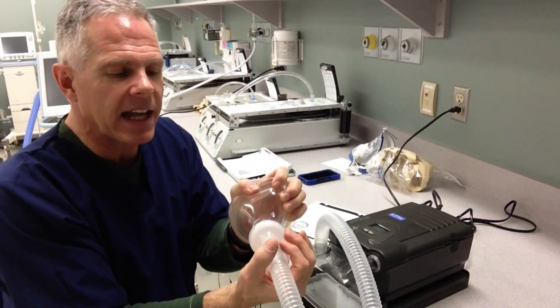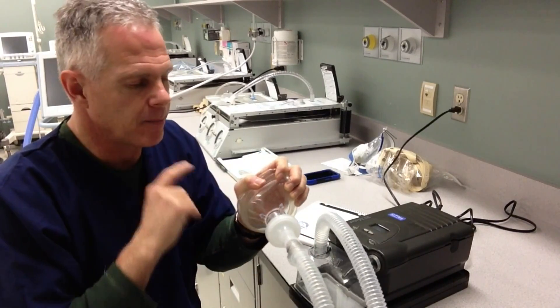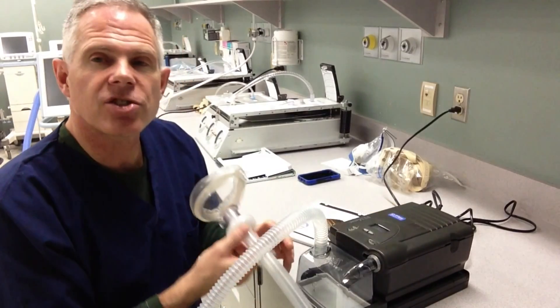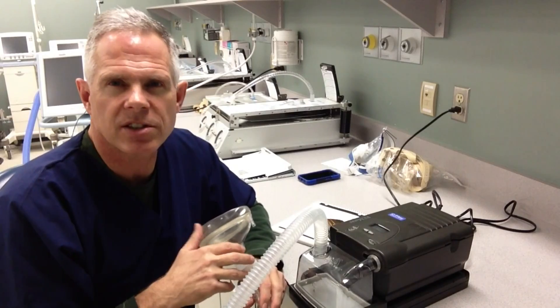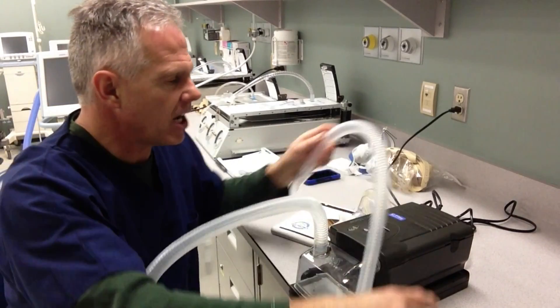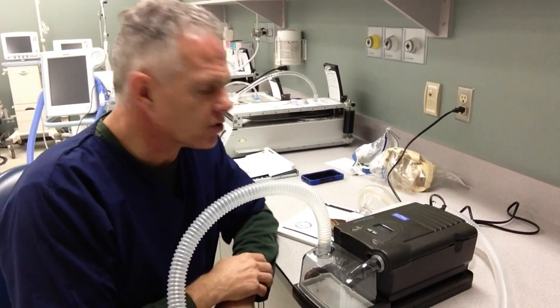That constant leakage is to make sure we are not re-breathing any of the carbon dioxide that builds up in the circuit, because of the dead space in here and we have no exhalation valve. We need that constant flow of gas so there's no buildup of CO2. It's a fairly straightforward device — thinking about how we teach our patients how to use it at home, that's why the settings can be locked out so the patient doesn't accidentally change them. This is the Respironics Remstar Auto and my name is Alan Prost — thank you for watching this demonstration.